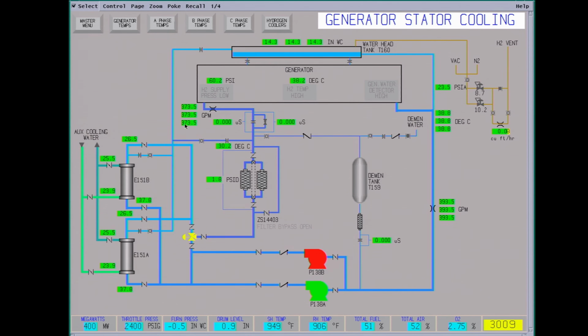These are your flows. Like most things, 2 out of 3 trip it. There's 3 level transmitters. Any 2 of them get below the trip point, it'll trip. You're measuring conductivity, micro Siemens. Little demin tank here. Just recirc pumps. They take the water, pump it through plate frame heat exchangers up to the unit, then it comes back out. This tank here is just your surge tank. Has nitrogen on it, since it's possible to get hydrogen back in here, so you don't want any oxygen in this system.